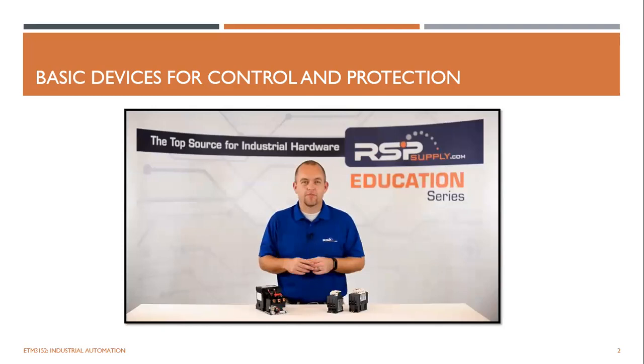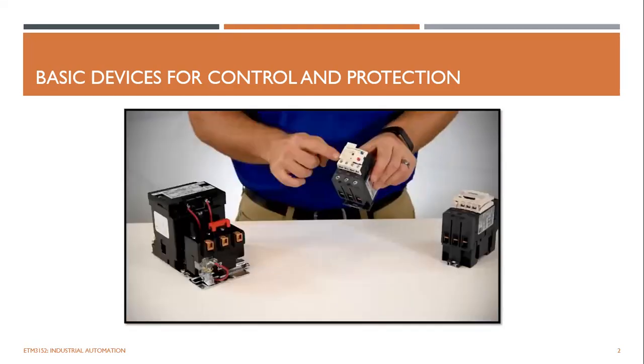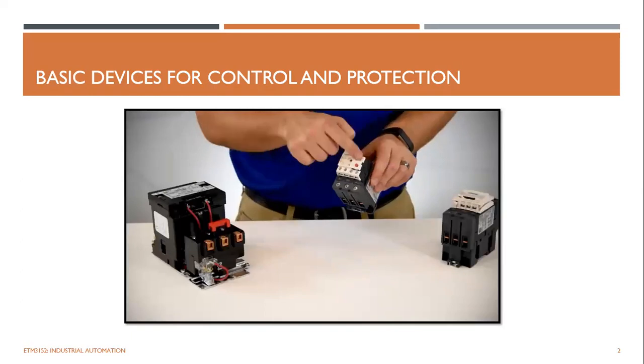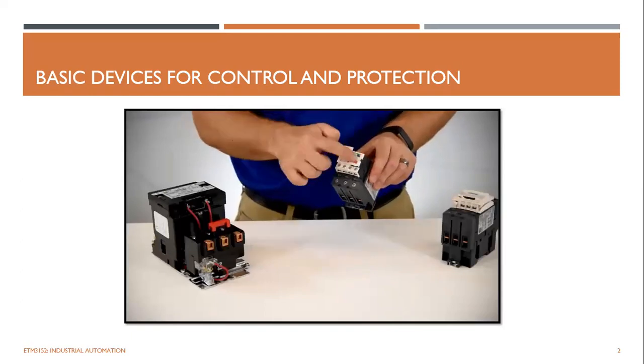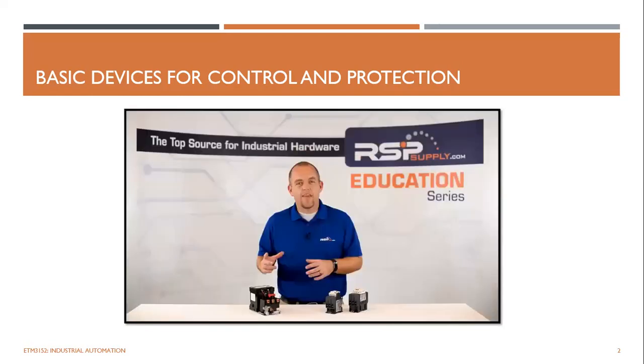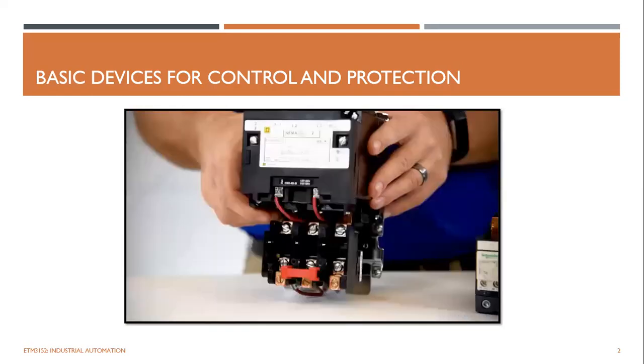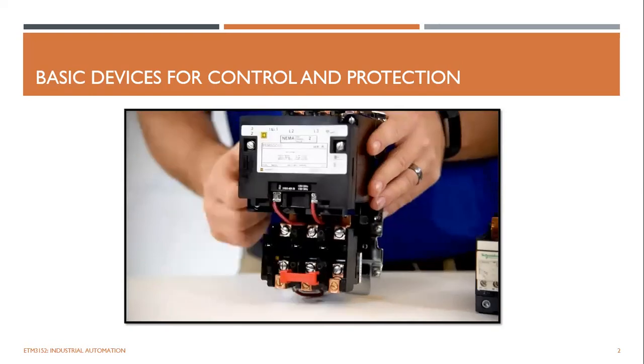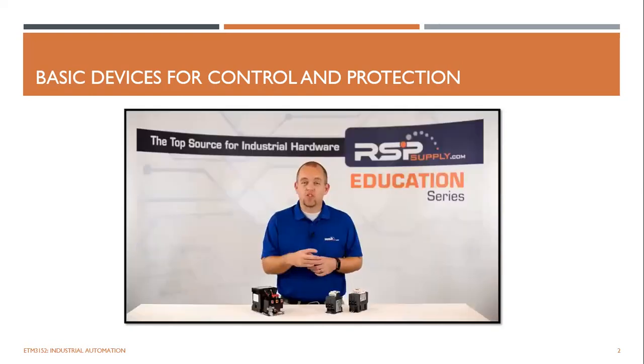So for example, on an electronic overload, we have the ability to set via a dial on the overload the amount of current that we want to allow to our motor for a specific period of time. On the thermal overload, we have the ability to insert a thermal element to our specific application and need. Once the overload has sensed that the motor has drawn too much current for a sustained period of time, it has the ability to disconnect the current that is passing through the starter. To meet protection needs, overloads have a time delay to allow small overloads to occur without breaking the circuit. This allows us to operate our motor without having it turn on and off frequently because of small overloads.